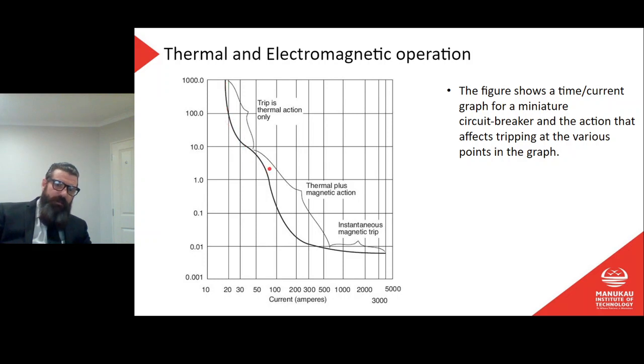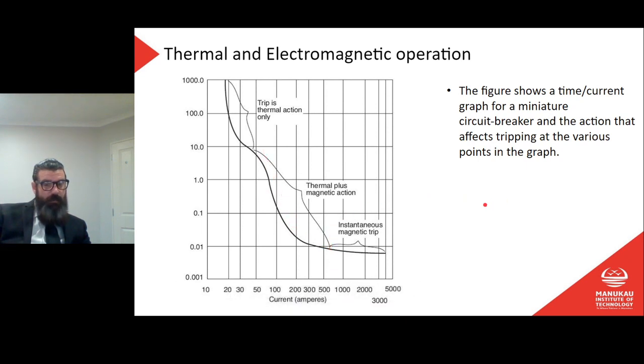And remember, our time current characteristic graph, inverse time current characteristic, tells us that as the current increases, the time it takes to trip is going to go down. So it will continue to go down, but still not very fast. We want it to trip a bit faster than that. Once we're getting to this 50 amp range, that thermal and magnetic action will happen simultaneously. And by the time we get to 500 amps here, our tripping time is 0.01 seconds, so very, very fast. Over those sorts of loads, we're talking about instantaneously tripping on the magnetic side. As soon as that current starts to flow, bang, it's going to trip.